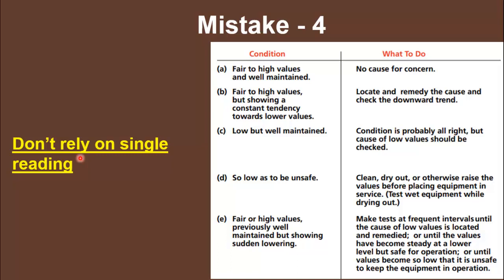Last but not least, a very common mistake is relying on a single reading. The correct procedure is to build a trend of the equipment's insulation resistance over time. By referring to this table, you can judge the insulation condition from the trend. If you are continuously getting higher values, there is no cause for concern. However, if the trend is continuously decreasing, the equipment may still be operational but something is causing the insulation resistance to drop — which needs attention.